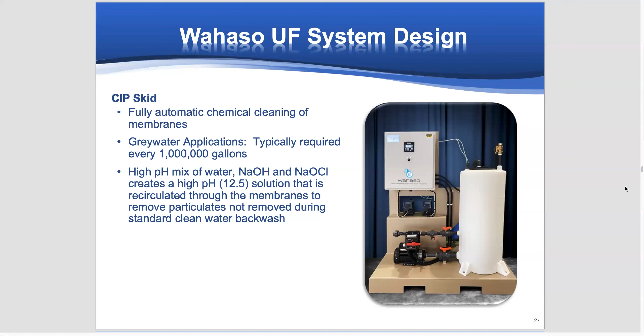And we have a skid that we offer that automatically does that. It automatically mixes up a high pH solution. It recirculates it through the ultrafilter system for 5 minutes. It disposes of that water. And then we run a clean water rinse to get rid of any chemicals remaining in the ultrafilter system, and it reverts back to normal operation. Again, it's all automatic and the operator doesn't have to do anything. I just want to make you aware that that exists.